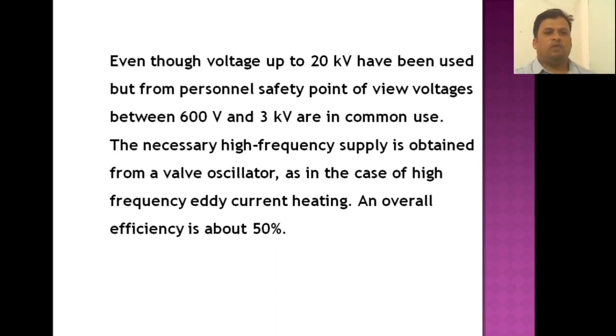Even though voltages up to 20 kV have been used, from the personnel safety point of view, voltages between 600 volts and 3 kV are in common use for dielectric heating. The necessary high frequency supply is obtained from a valve oscillator, which changes the frequency from low to high, as in the case of high frequency eddy current heating, and the overall efficiency is about 50% here.